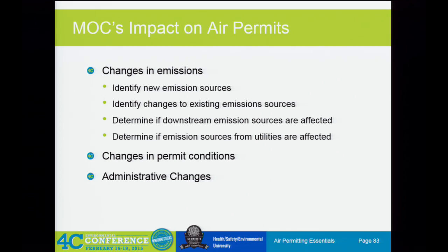It's more accurate than our previous monitoring strategy. And a lot of times, if it's as good or better than what you were doing before, the state agency will have no problem approving updates in your permit conditions to allow you to make those types of changes. So that's a bullet point that's probably a little more rare in terms of the MOC process, but it can occur, and that's something that you should look for.